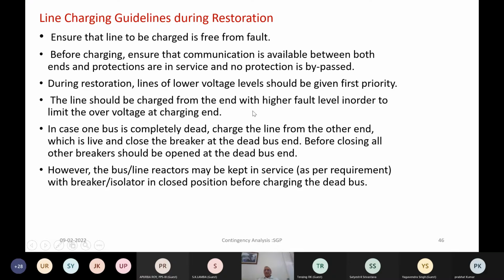The line should be charged from the end with higher fault level in order to limit the over voltage at the charging end. We had mentioned, especially if the line length is long. So when you charge the line for the first time, you may experience over voltage at the remote end. In case one bus is completely dead, charge the line from the other end, which is live, and close the breaker on dead bus. So you should have dead bus charging permissive. Otherwise, normally breaker will not be allowed to be closed without sync check. So the sync check scheme should have dead bus charging facility.